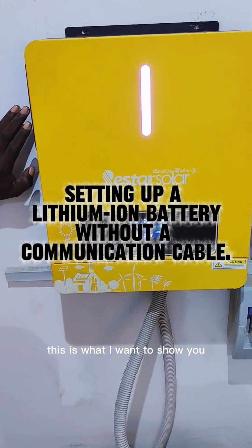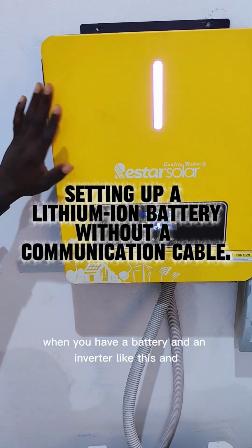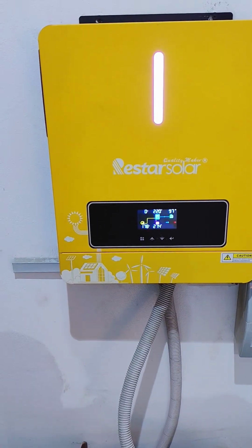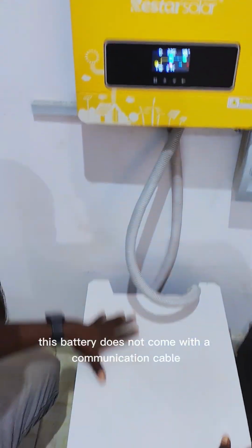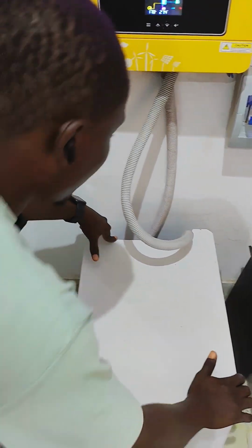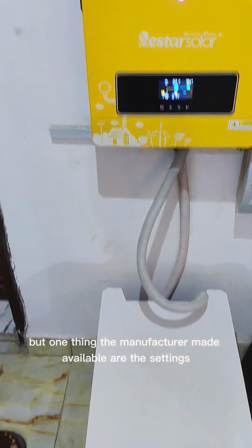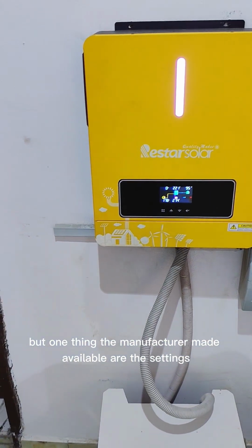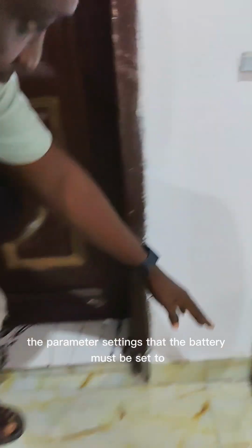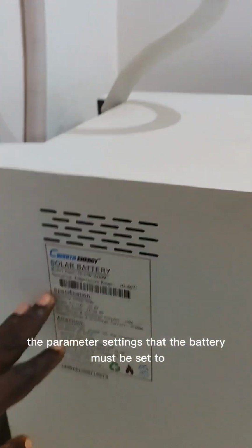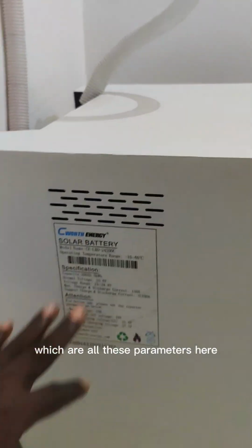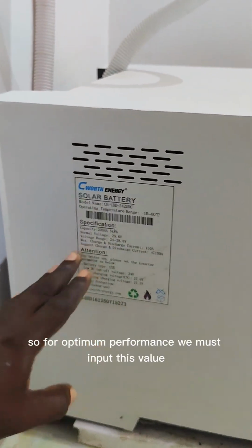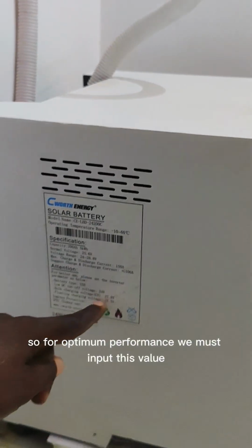This is what I want to show you. When you have a battery and an inverter like this, and this battery does not come with a communication cable, one thing the manufacturer made available are the parameter settings that the battery must be set to, which are all these parameters here. So for optimum performance, we must input these values.